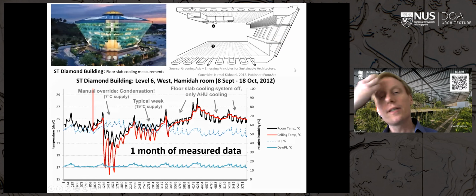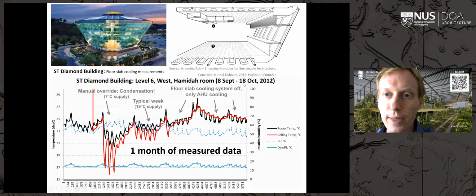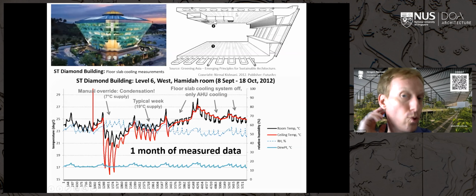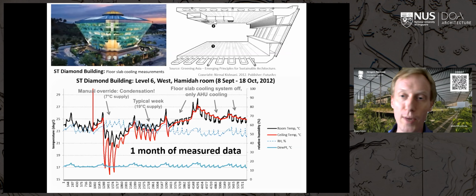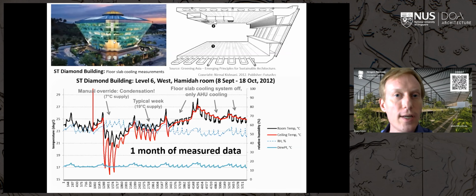So a lot of people ask, don't you have condensation when you cool down the structure of the building? And that is definitely a risk. So that's why this system is not suitable for any building, and especially residential where you often open the windows. I wouldn't recommend it. But for this kind of office building where windows are typically not opened, there are some windows that can be opened, but they never are, it's okay.